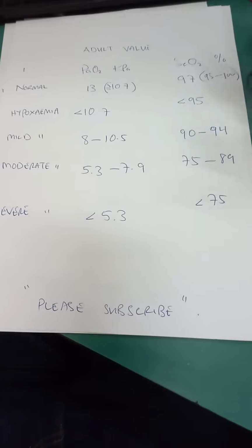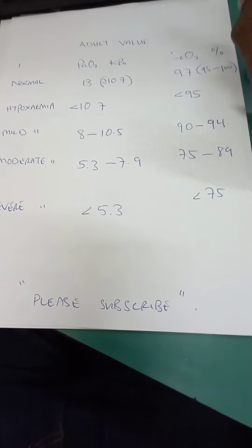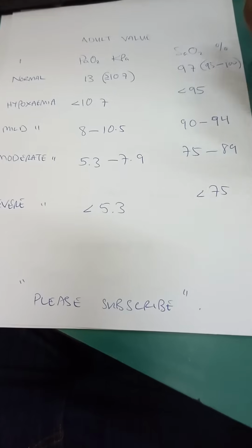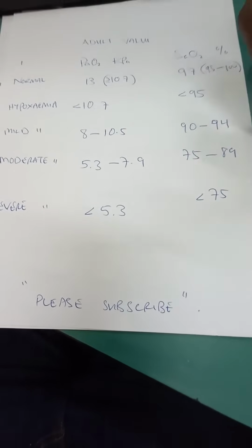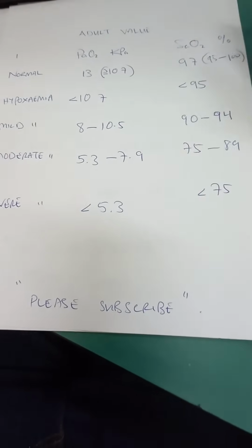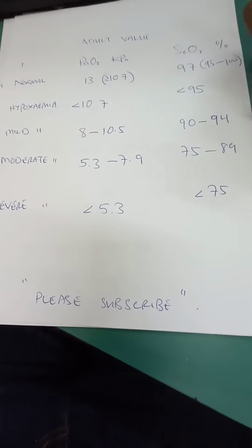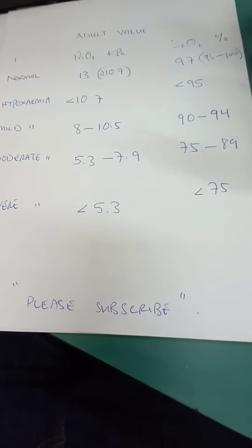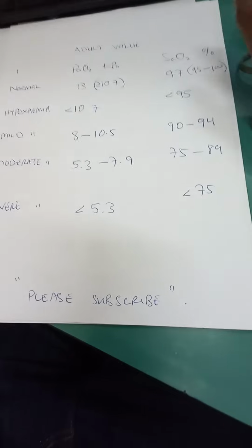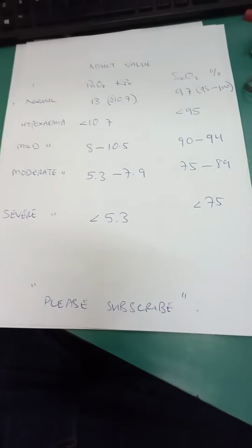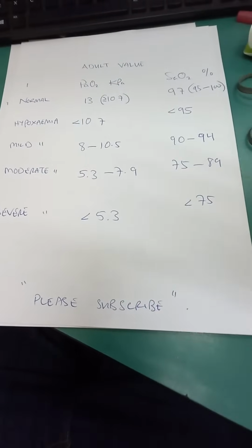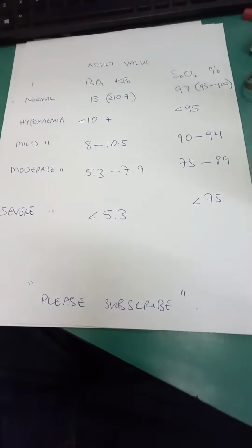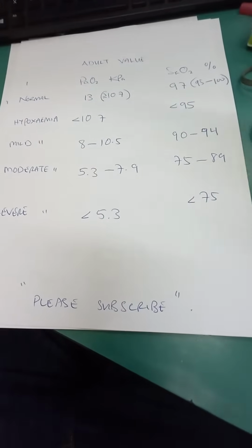The oximeters work on the principle that desaturated hemoglobin and oxygenated hemoglobin absorb light of different wavelengths. So the current device uses two wavelengths and measures the absorption in the pulsatile element of the blood flow, thus producing a measure of the oxygen saturation of arterial blood separate from the non-pulsatile venous blood.